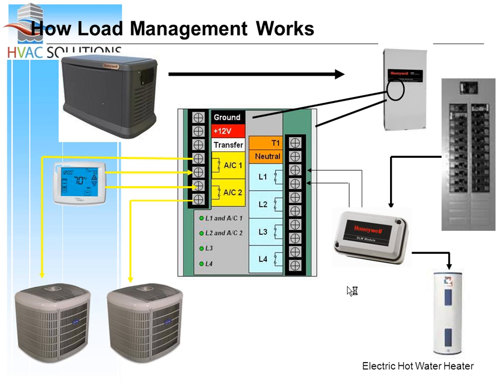What if they say, I really like my air conditioner, but I don't like it quite as much as my hot water heater? Not a problem, we'll put the hot water heater on L1 and move the air conditioner to AC2. In that circumstance, we'd turn on the electric hot water heater first, then go to AC2. The point is you can set your priorities, or leave it on the customer circuit breaker panel, but the generator has to be big enough to handle the load.